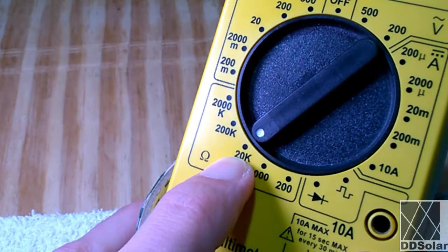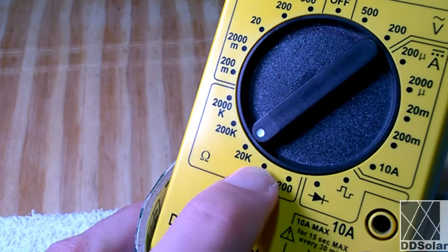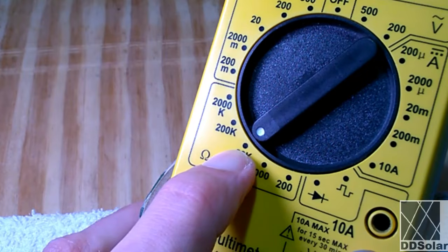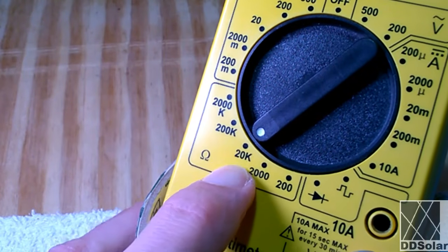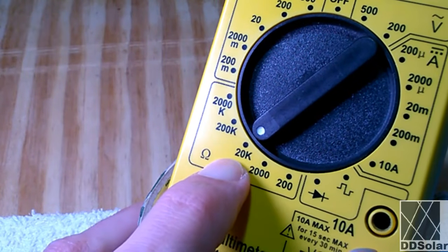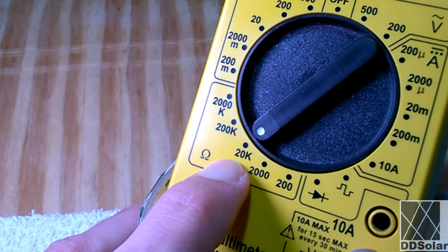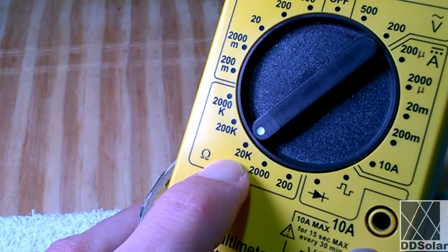Now, if you were to plug the meter into an extension cord and you had to come all the way up here to get a reading, it's time to throw that cord away, because an extension cord would never be 20,000 ohms or 10,000 ohms. You want it to be under 1 ohm, and a tenth of an ohm, half an ohm, would be probably the very most I'd be willing to accept.